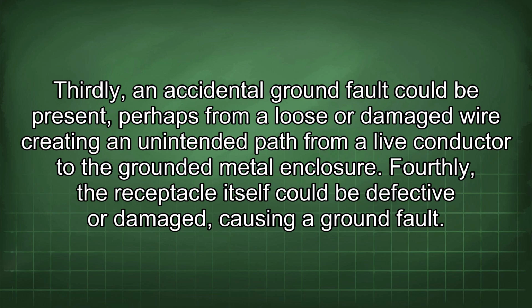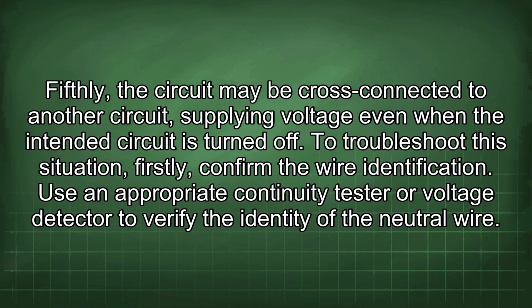Fourthly, the receptacle itself could be defective or damaged, causing a ground fault. Fifthly, the circuit may be cross-connected to another circuit, supplying voltage even when the intended circuit is turned off. To troubleshoot the situation, firstly, confirm the wire identification. Use an appropriate continuity tester or voltage detector to verify the identity of the neutral wire.